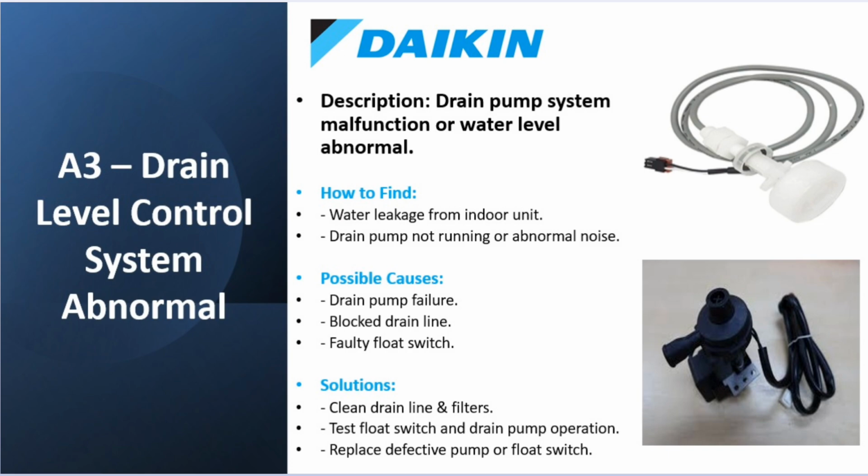A3 is for drain level control system abnormal. If you see water leaking or hear weird noises from the drain pump, it could be blocked or broken. Clean the drain line and filters, test the float switch, and if needed, swap out the pump.